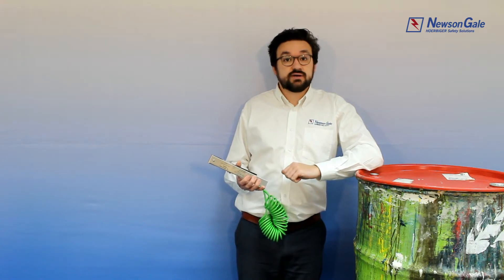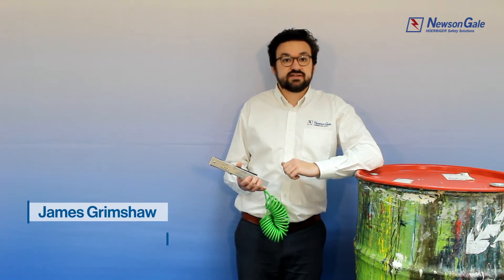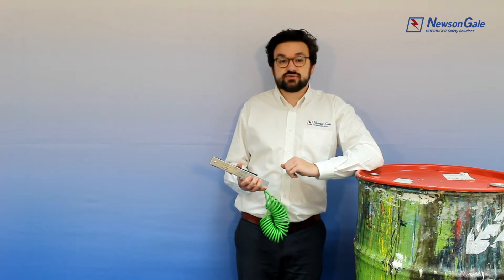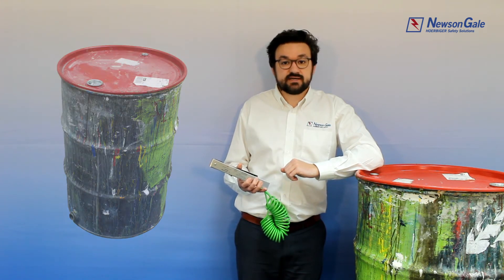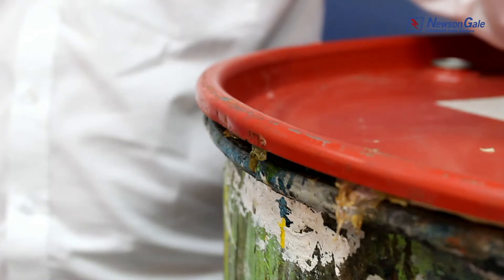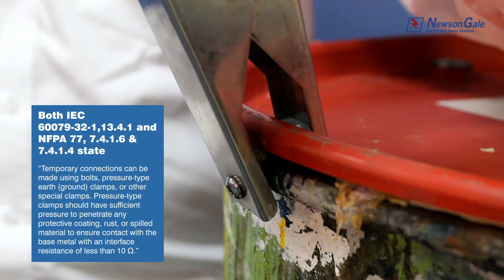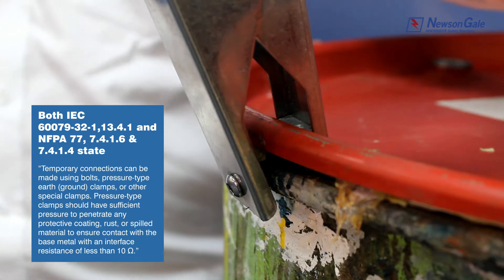In this short video we're going to discuss the advantages of tungsten carbide tips fitted to Newson Gale's grounding clamps. In most industrial processes, layers of deposits can form, inhibiting reliable safe static dissipation. Biting into the surface of any item of plant equipment securely is imperative to providing a reliable low resistance earth connection of 10 ohms or less.